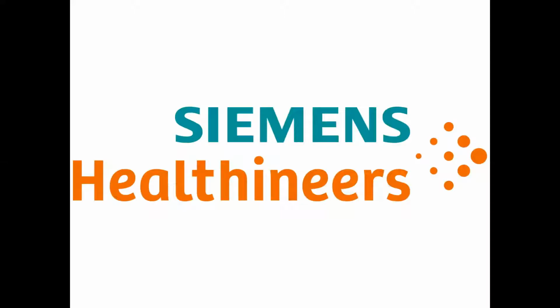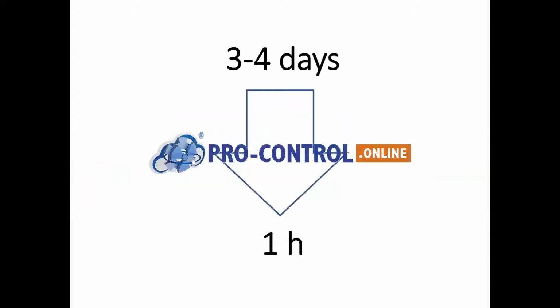A great example of how powerful our solution is is our case with Siemens in Poland. Using only four kits of the phantom I showed you before, and our software, we are able to reduce the downtime of units, C-arms in this case, from 3 to 4 days to an astonishing 1 hour.